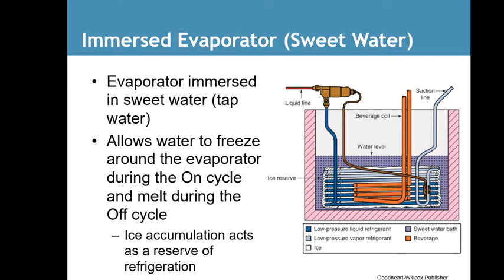Immersed evaporator, sweet water. Evaporators immersed in sweet water, tap water, allow the water to freeze around the evaporator during the on cycle and melt during the off cycle. They're usually used in things like soda machines.